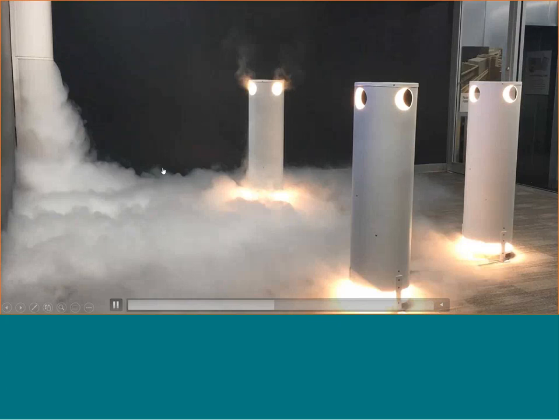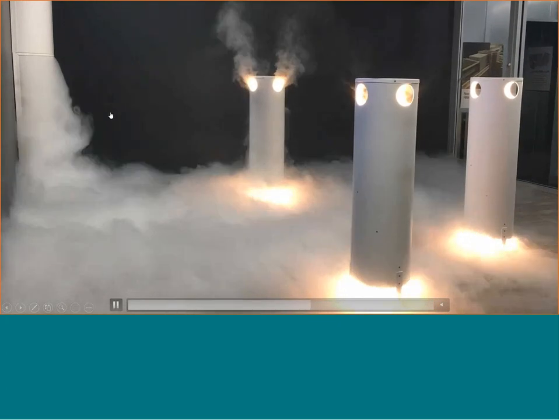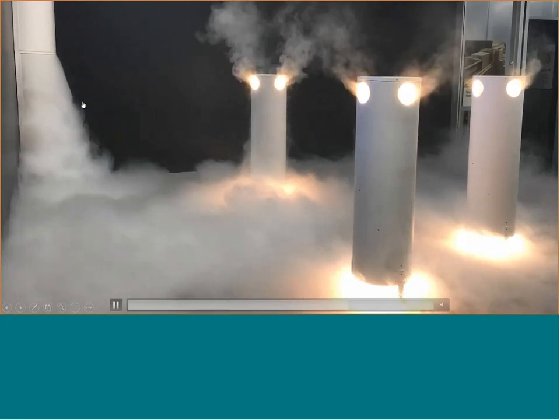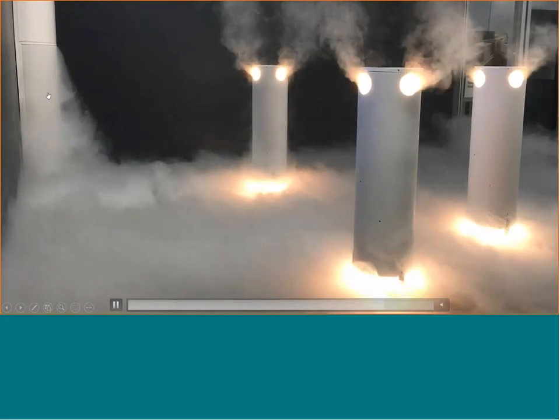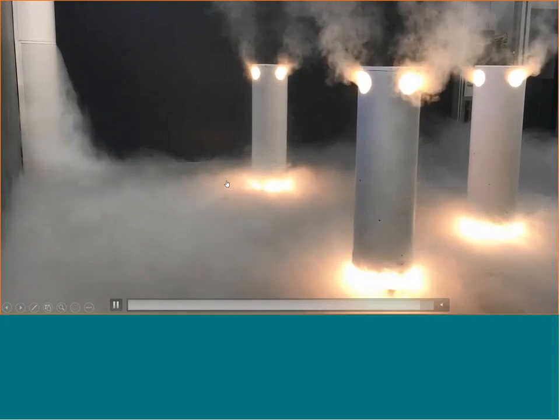So it's a really quiet system. You're not pushing through at high velocity with all the momentum in the space driven by the diffuser. Instead, it's really natural convection that's moving the air throughout the space. So there's a really low static pressure drop across these diffusers to get this done.